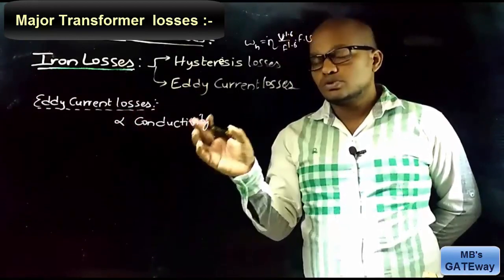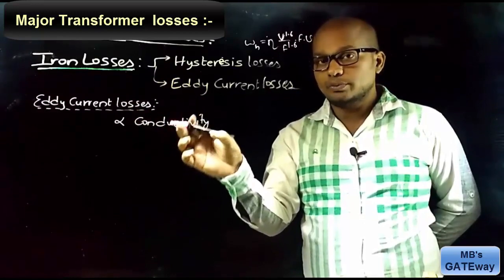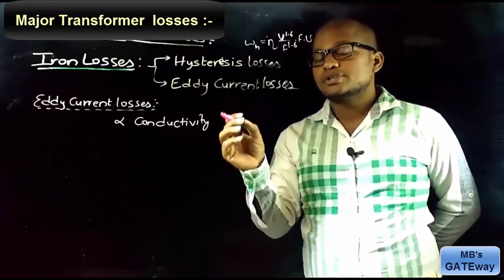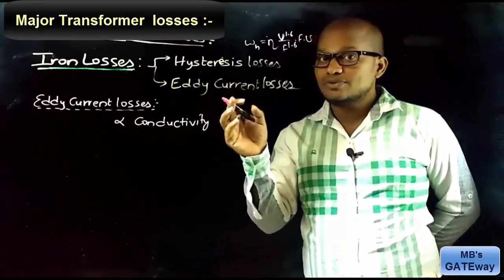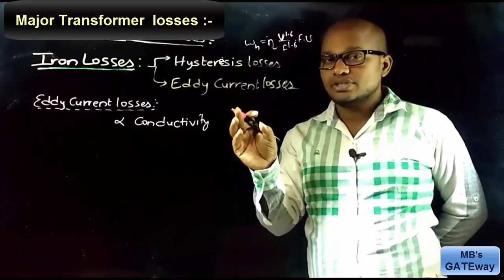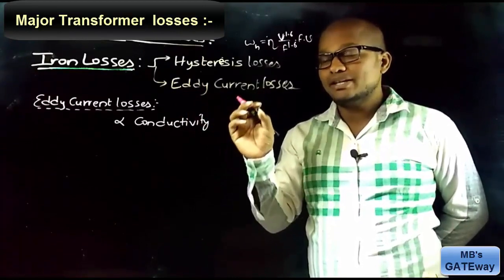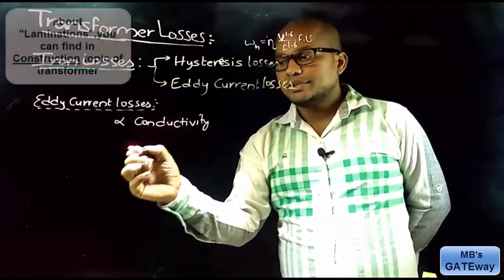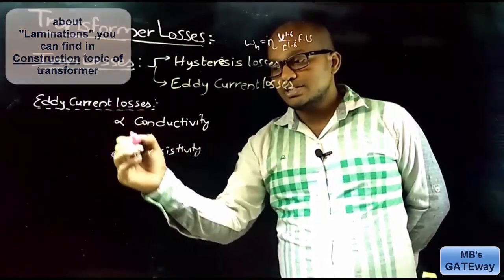Eddy current losses are directly proportional to the conductivity of the core material. To reduce eddy current losses we need to decrease the conductivity, i.e., increase the resistivity of core material. This is done by adding 3 to 4 percent silicon to the CRGO core material. However, adding silicon alone does not reduce eddy current losses to a large extent; they are much more reduced by laminating the core.